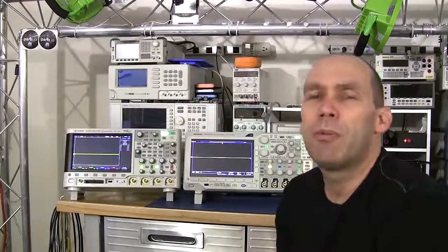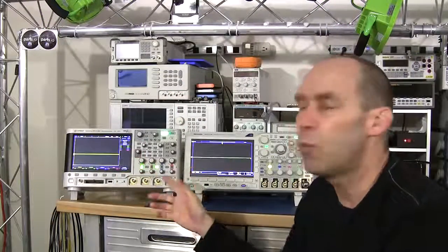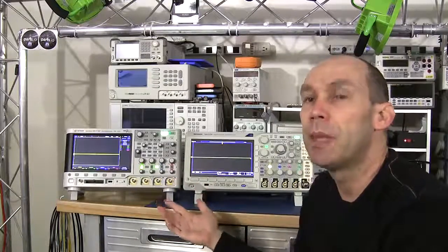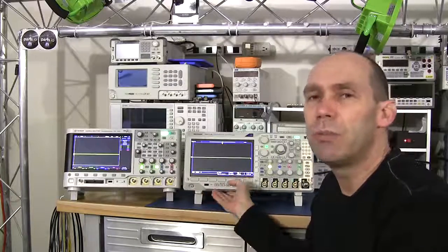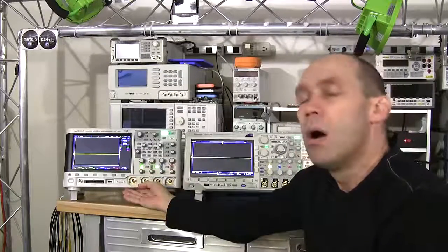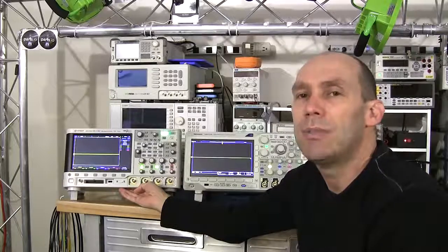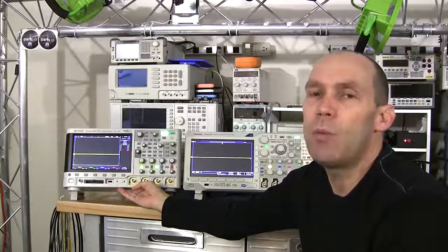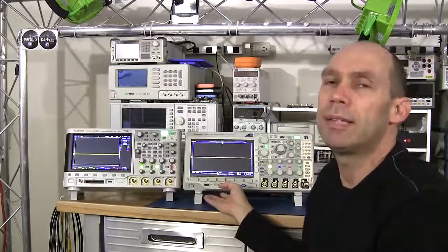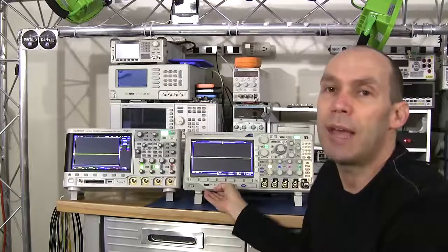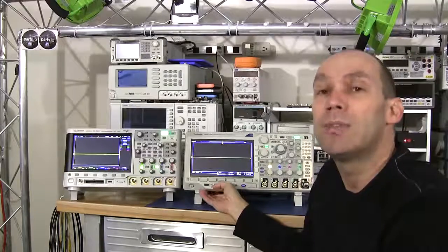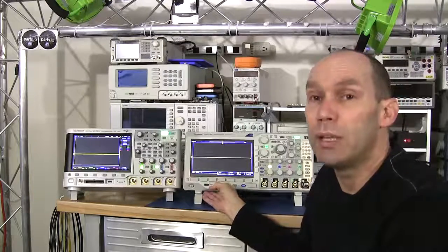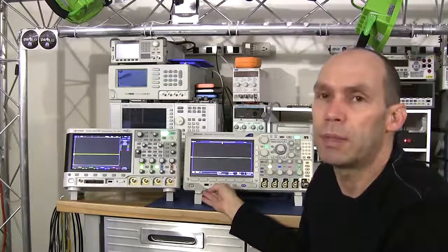Now, the other key performance feature to note between these two is the waveform updates, and that is certainly based around their computing architecture. The Tektronix relies on more traditional computing architecture, while the Keysight has got its own custom ASICs to help it perform very well. The Keysight can deliver over 1 million waveform updates per second, while the Tektronix does about 280,000 waveform updates per second in its fast acquisition mode. Although there are some compromises that need to be noted when it is running in that fast acquisition mode, which we'll look at once we get to the bench.